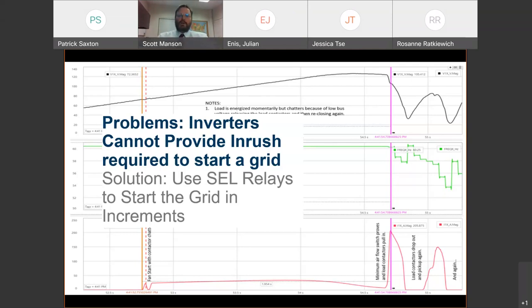Yeah, so the bottom is the current. You can see the surge current, this first lobe of surge current at approximately time 55 seconds. The surge current in red went up as the load turned on. The contactor chattered because the voltage collapsed on the top. And now the load and the inverter were oscillating. This is like an oscillation of your load, oscillation of your lights. This is very damaging to electronics. And we've seen inverters destroy themselves in this behavior. So we use relays to prevent that phenomenon.